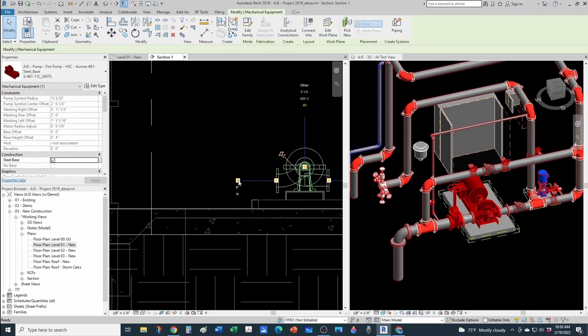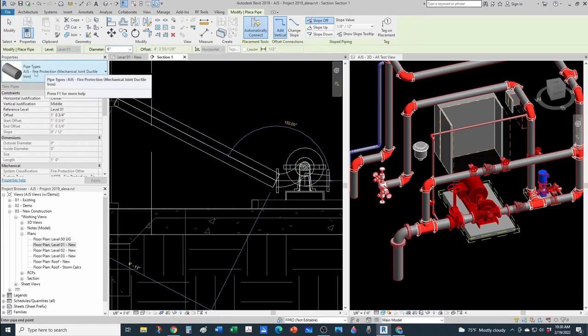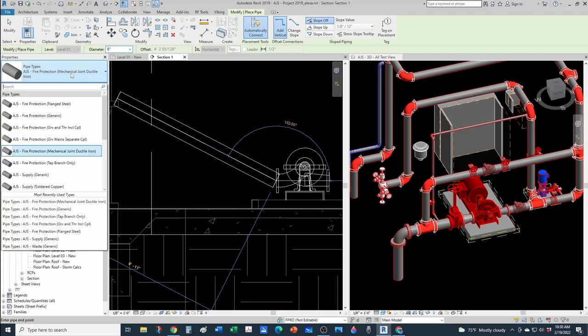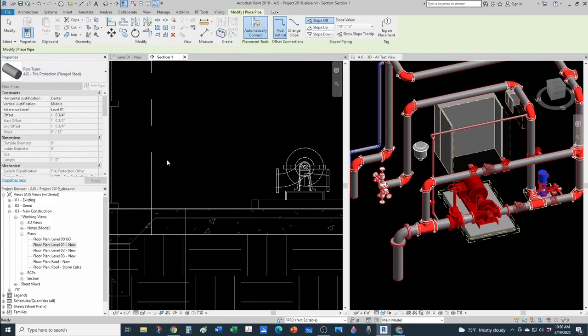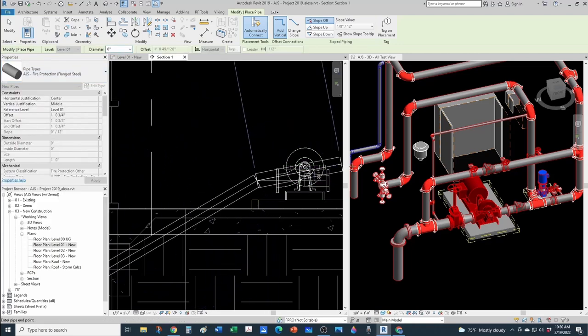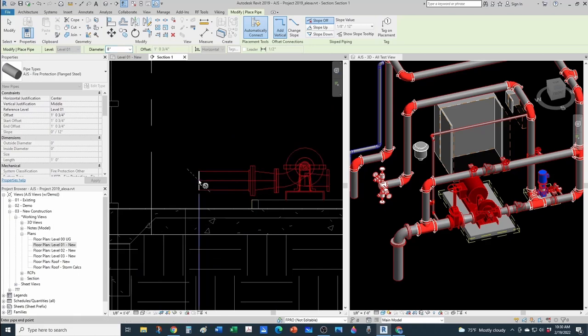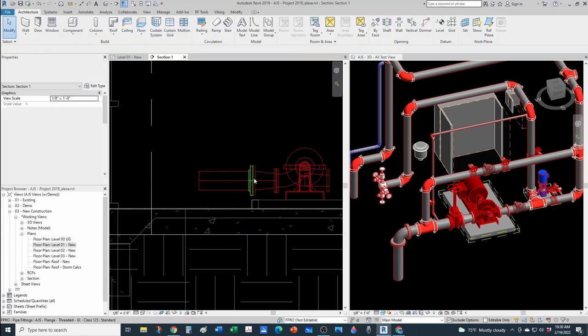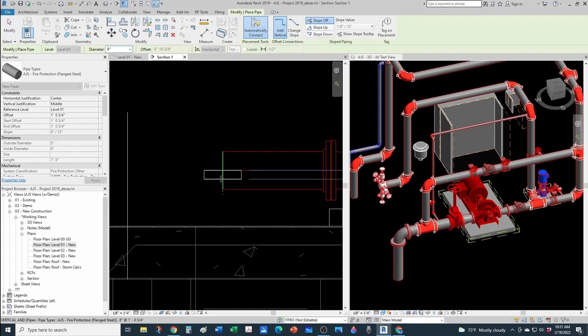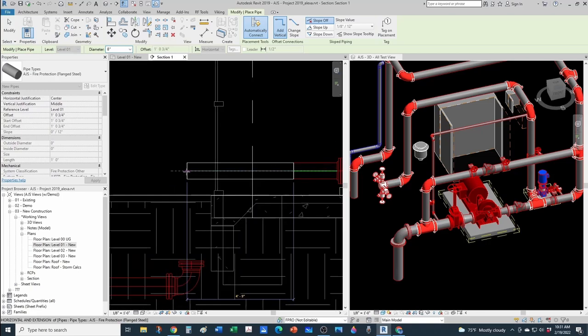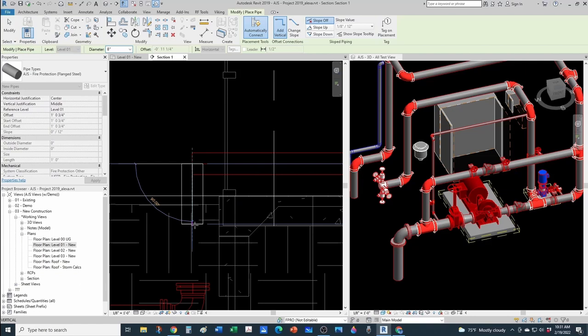So for now, let's just see, I need to change my pipe type from mechanical joint to flanged. Right, has to be a flange steel, and as we saw per NFPA 20 requirement, we need to have an 8-inch suction line. So I need to change from 6 to 8 right here, and then take it out, and that's my reducer right here. Right, and you're gonna be switching back and forth between different pipe types depending on what you want to connect.